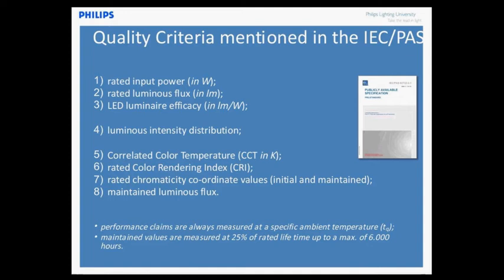What is mentioned in the international standard are those eight quality criteria: the rated input power, rated luminous flux, and from those we can calculate the LED luminaire efficacy. Some people question whether lumens per watt for a luminaire is really the way to go forward, but it's used today. You will also find luminous intensity distribution - how the light comes out of your luminaire - which is the input for your lighting calculations. And there are four more quality-of-light related parameters: CCT, CRI, but also the rated chromaticity coordinates and the maintained luminous flux. For those familiar with the lighting industry, it is not really something new.